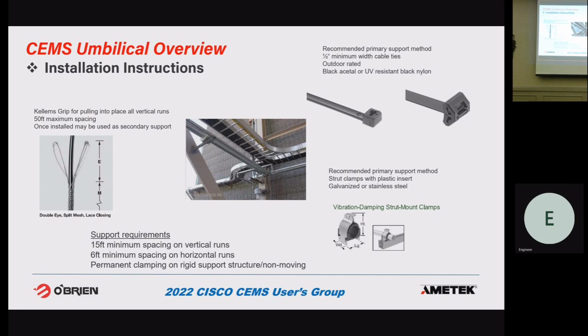Another style of clamp I like is for connecting to unistrut. It's a pipe clamp with a plastic insert and a single pinch point, so it fits into the unistrut, and they're sized about every quarter inch. You'd put that around the bundle and then fit it into the unistrut.